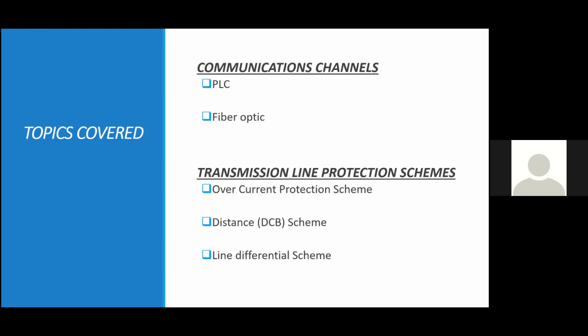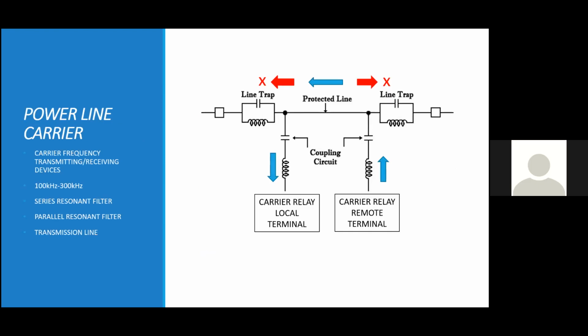We'll start off with the basics of communication channels. Firstly, I'll talk about the power line carrier channel. For this setup to work, we need two relays, one at the local end, other at the remote end. We also need a line tuner circuit, comprised of a series resonant filter. In this communication channel scheme, we use the protection line as our communication medium, so you don't need an external or extra communication channel to implement this scheme.